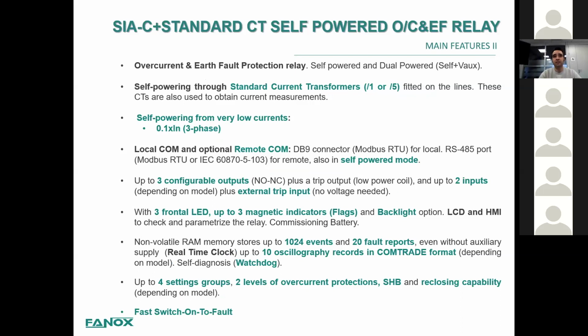The characteristic of this relay is that it works with standard current transformers, and the self-powering level is very low. It means that we can activate the relay starting from 0.1 times the nominal current. That means if you have a 40/1 amp CT, we are going to power up the relay starting at 4 amps on the primary side, okay?